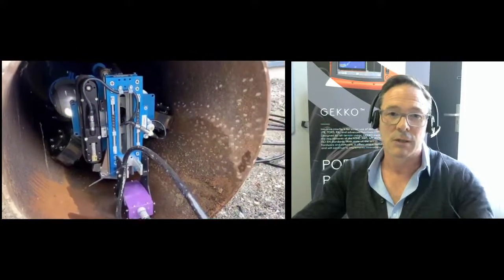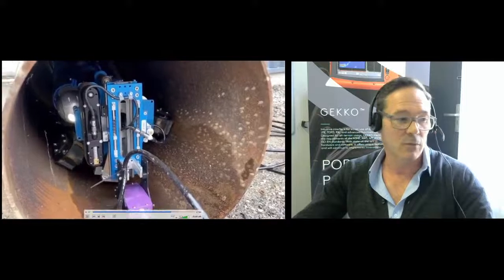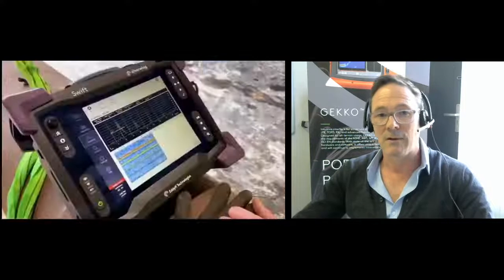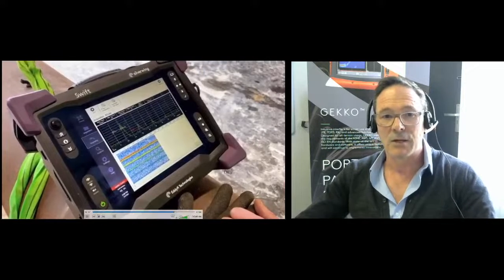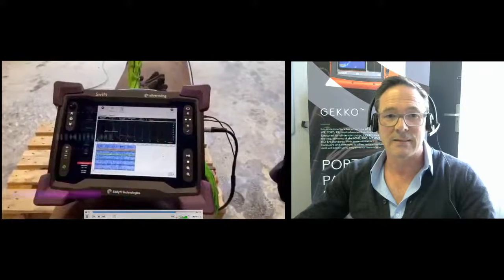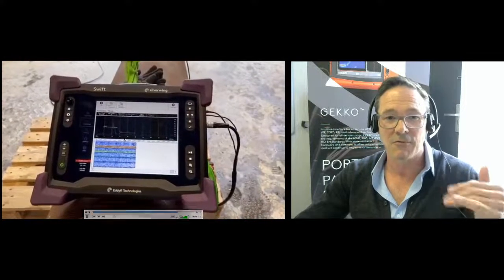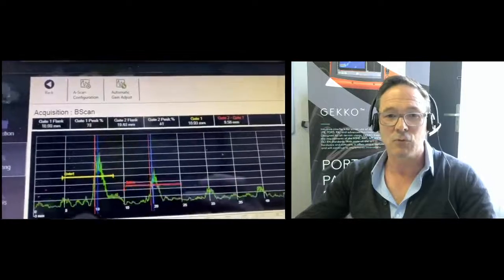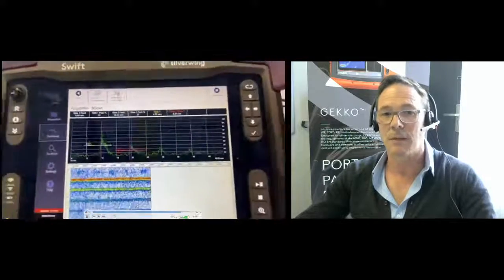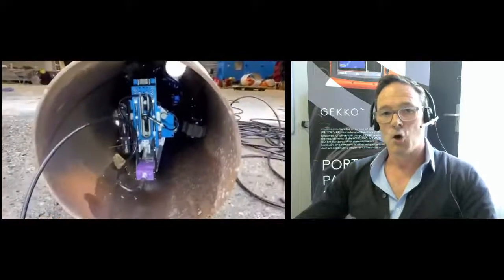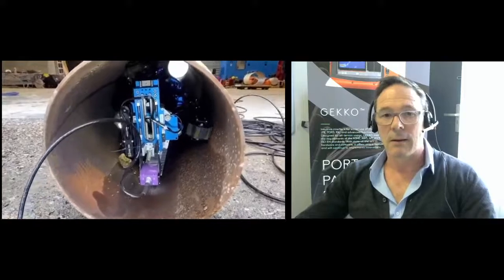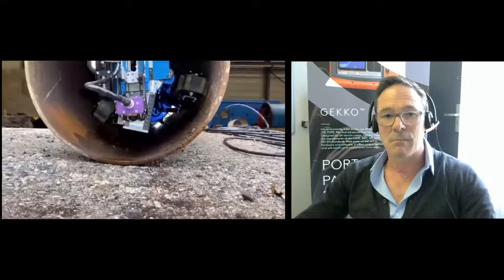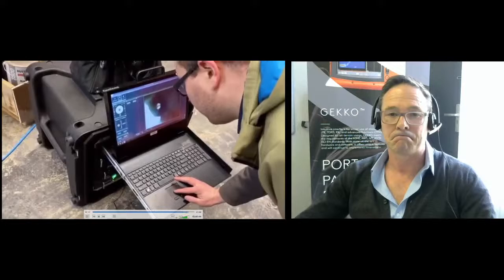This is the control unit outside the pipe, controlling the whole thing from quite a distance. We can see the B scans being collected, and you can nicely see the floating gates adapt to variations in coupling as the probe makes a measurement.